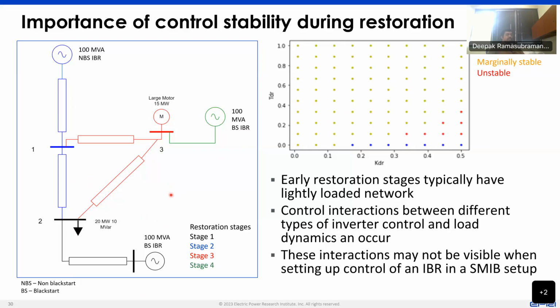Early stages of restoration are typically lightly loaded and also have higher voltage levels. Which means that the inverter-based resources that we are operating in this early stage of restoration should absorb reactive power, and that can have stability challenges associated with it. We've also seen in our studies control interactions occurring between different types of inverter control and different types of load dynamics. So load dynamics is extremely important to consider when you're doing a restoration evaluation, because depending upon the type of load that you're energizing and picking up, it can have an interaction with the inverter control that you're looking at. And some of these interactions are not necessarily visible when you set up an inverter in a single machine infinite bus setup and look at its design of its control gains and its control loops.